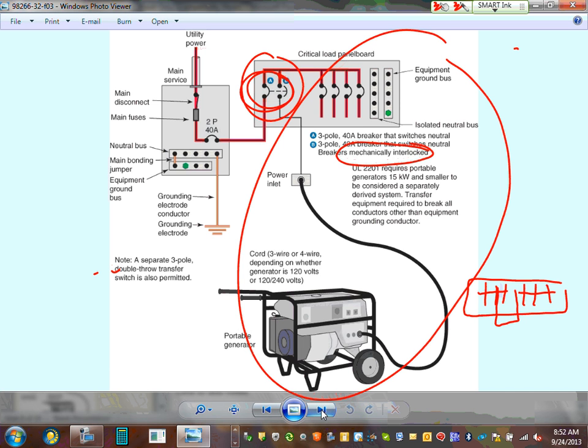Now we're running on utilities. So normally, your load will be up and running on utilities. When you lose the power, go start the generator, plug in your generator, twist it, go down to the basement, flip those mechanically interlocked 40-amp circuit breakers, and you are up and running. You're up and running on the generator.